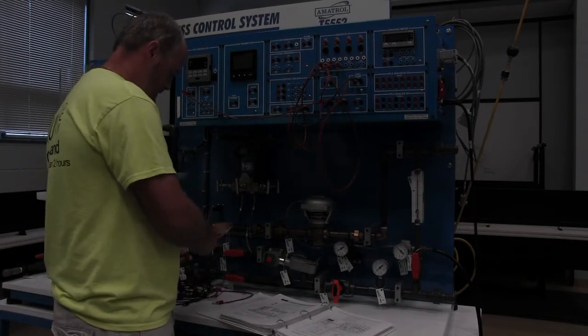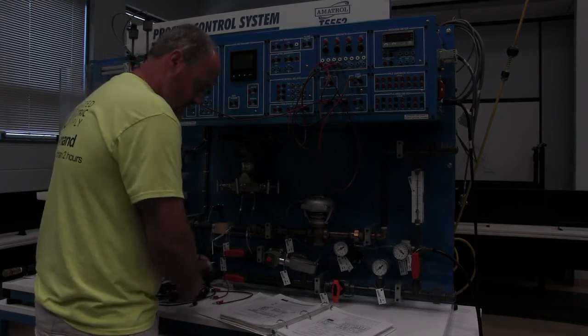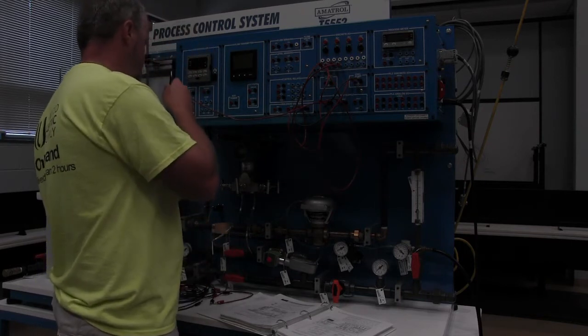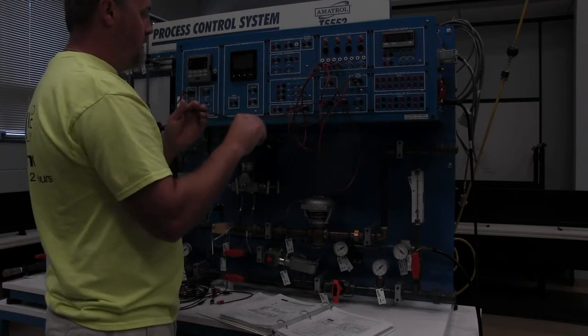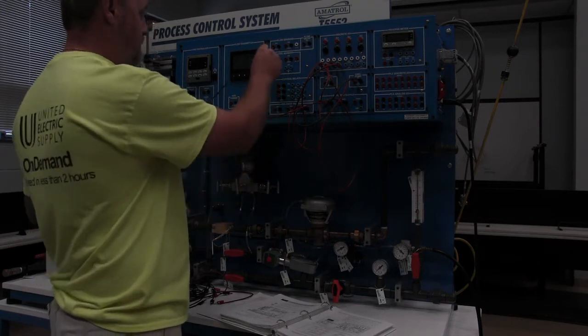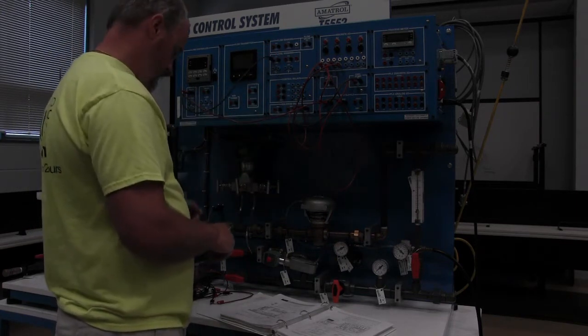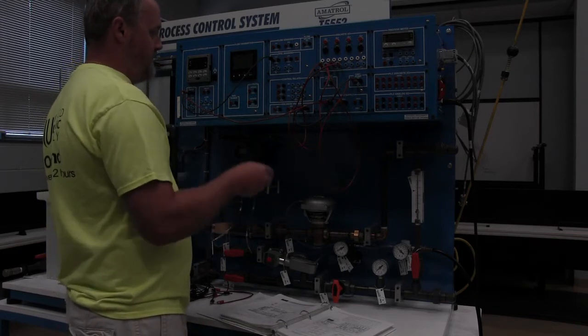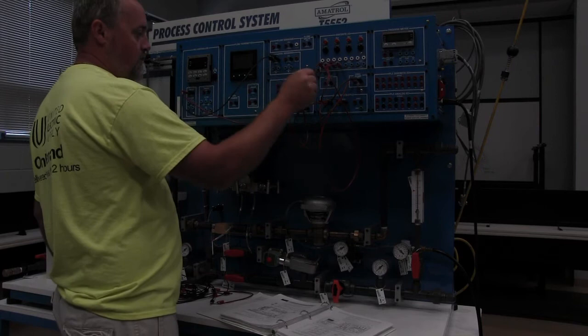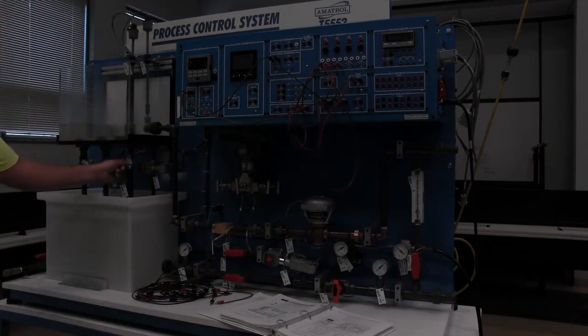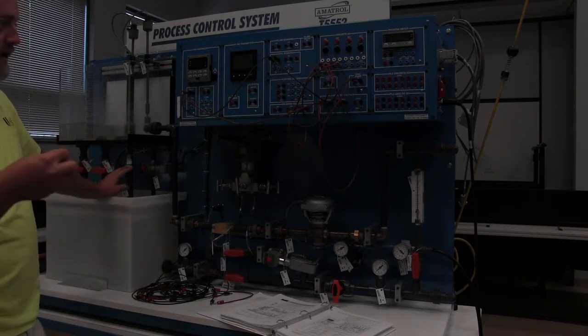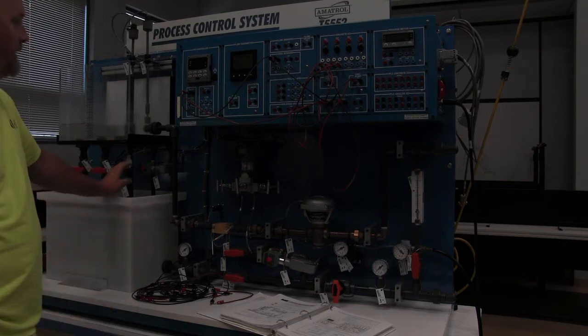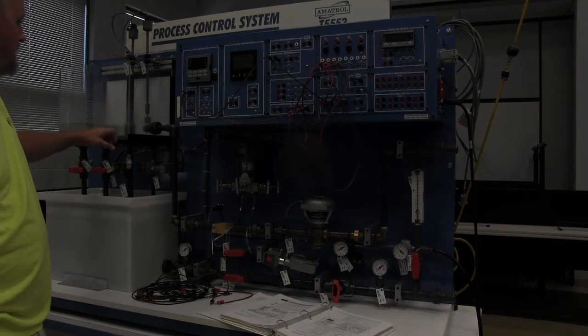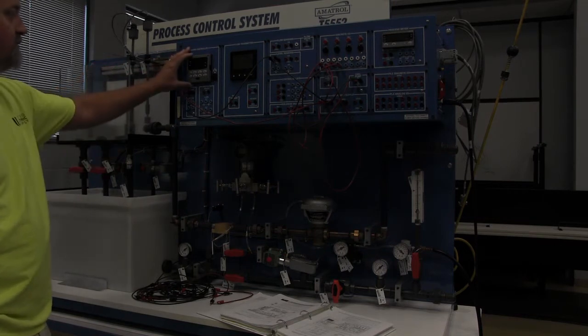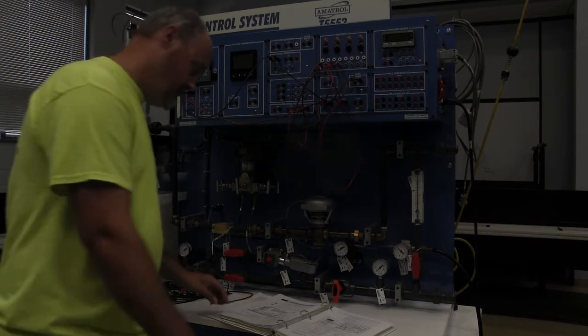From the negative of AI1, we're going to go to LT1, which is a level transmitter. And then we're going to take the LT1 negative back to the power supply. So now, instead of using floats, we are using a level transmitter. They're used in a lot of water tanks. It will take pressure and convert it to the level for you, and that's what we'll do through this controller. And it will actually increase and decrease the level based off of a level set point rather than floats.